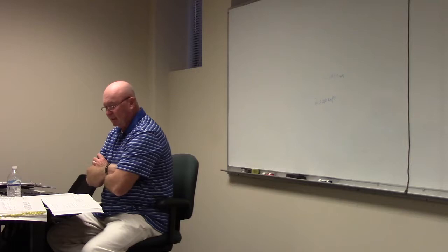900 MCM. Anybody ever put any 900 MCM in? Me neither. Option number 2 says it'd be 5 runs. That's 400 amps per leg. What size wire would that be? 600 MCM. Still pretty expensive, isn't it?